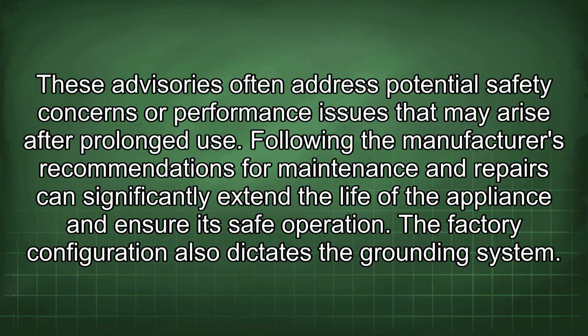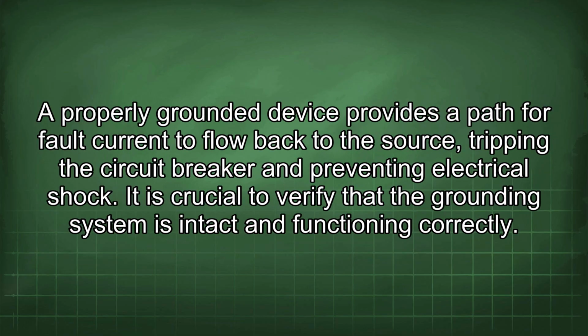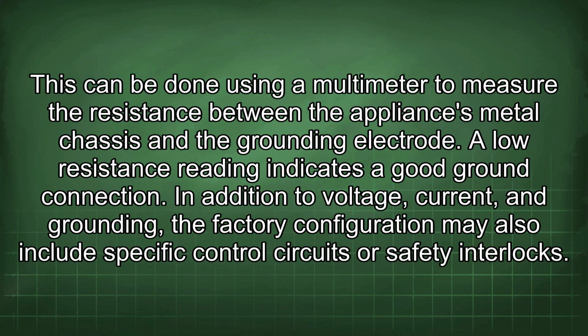The factory configuration also dictates the grounding system. A properly grounded device provides a path for fault current to flow back to the source, tripping the circuit breaker and preventing electrical shock. It is crucial to verify that the grounding system is intact and functioning correctly. This can be done using a multimeter to measure the resistance between the appliance's metal chassis and the grounding electrode. A low resistance reading indicates a good ground connection.